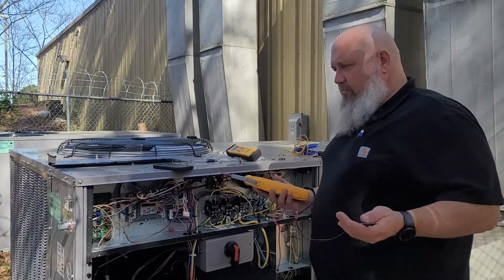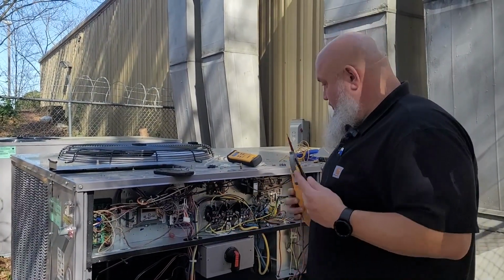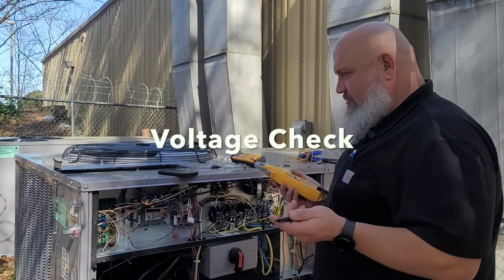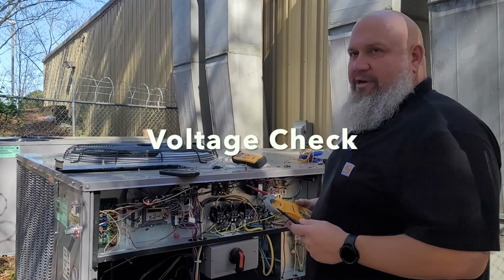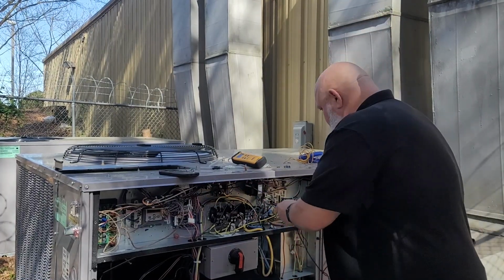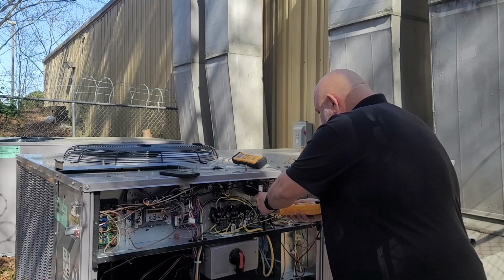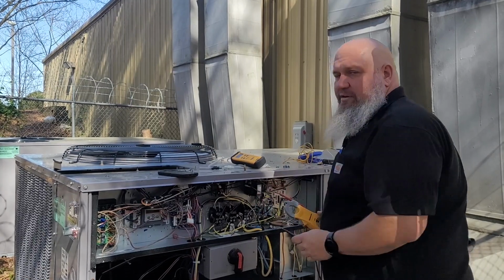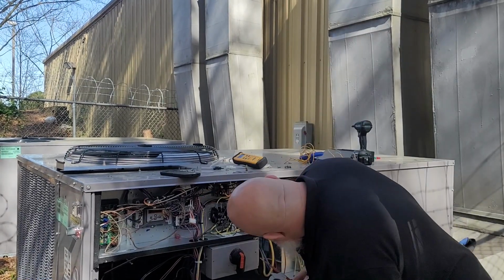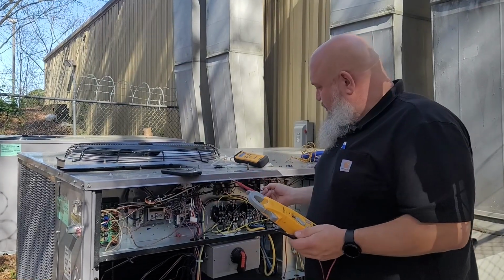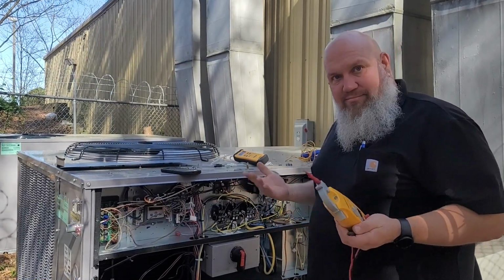The first thing I do when I'm checking out a unit is I always check the voltage. You should always make sure you're doing it safely with your meter. And on this unit, we're 210 volts. You always want to check your main transformer because it's multi-tap.